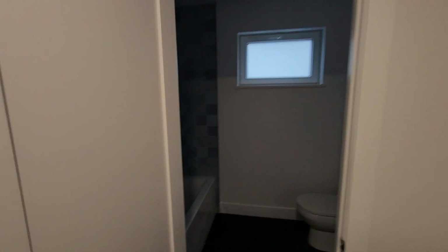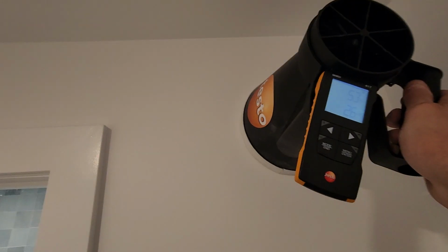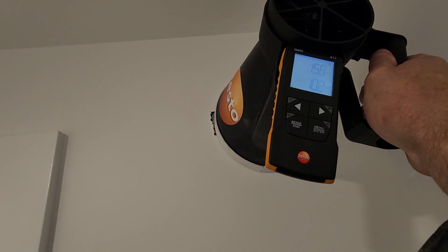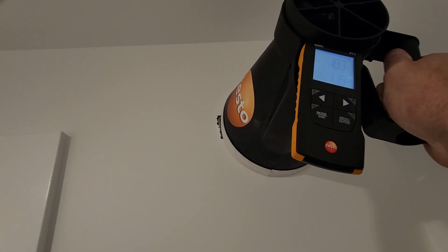And for something like a bathroom, what we can do, this room is split. So of course, we have the shower in here, and the toilet. Then out here, a couple of sinks. And then on each side, we ventilate, and we're extracting air again on these units. So I'm going to split it between the two. And what we need is, for code, we need at least 20 CFM continuous. And for passive house, it's recommended 24 CFM continuous. So we get 12 on each end, and we're good to go.